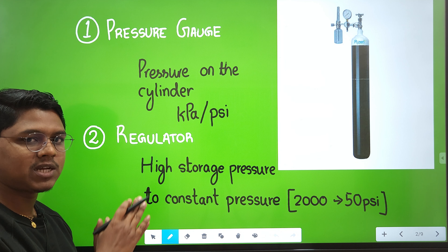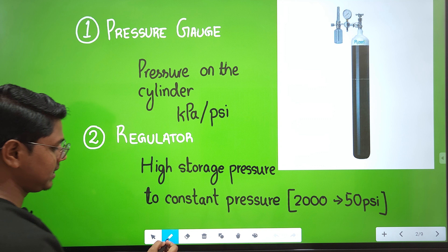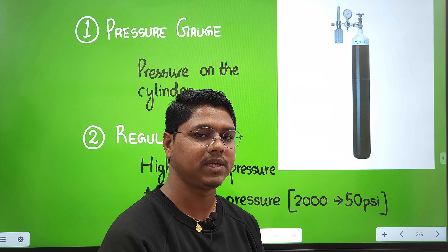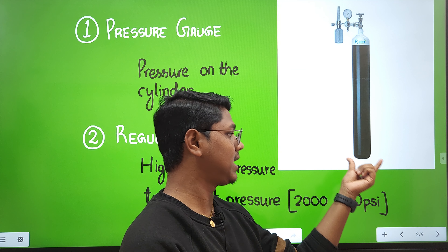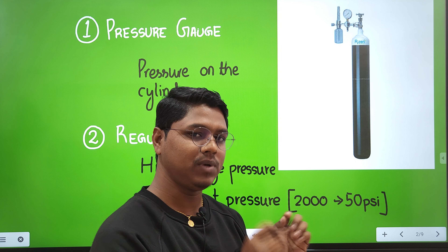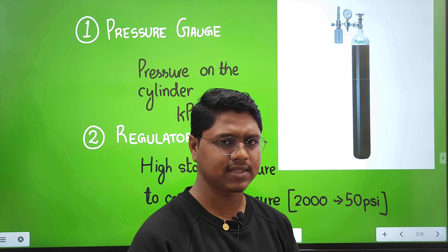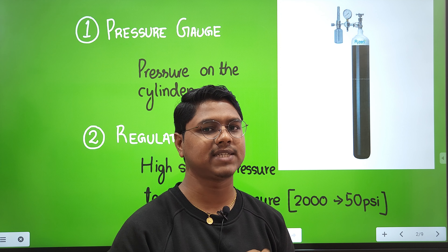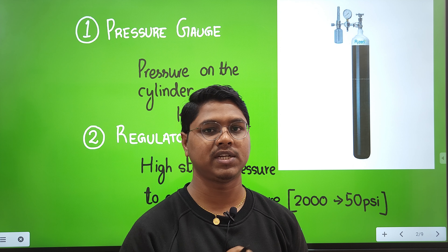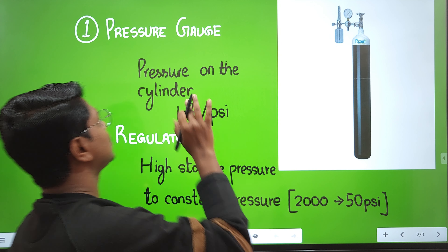Now, coming to the parts of the anesthesia machine — at the end I will show the full machine and all its parts, but first we should know the individual parts. The first part is the pressure gauge. A cylinder is provided which gives the fresh gas flow — or in technical terms, it provides the carrier gas, which takes the volatile anesthetics into the breathing circuit. This is the oxygen cylinder; it is black with a white neck.